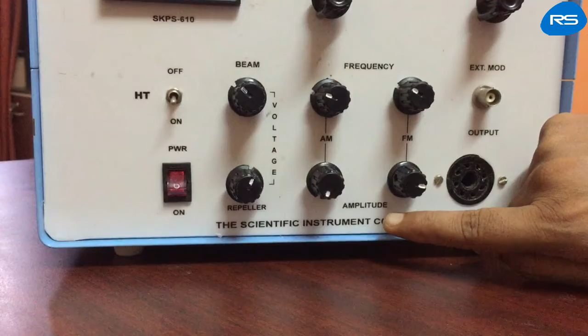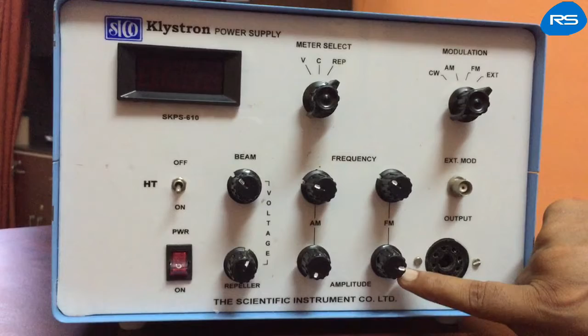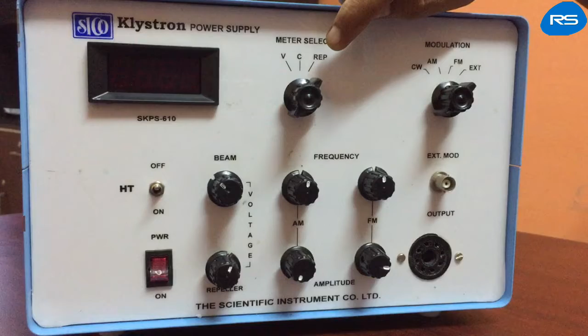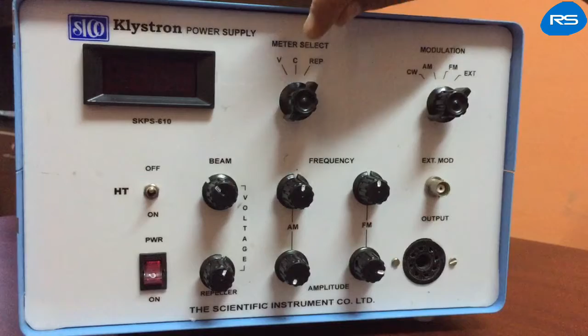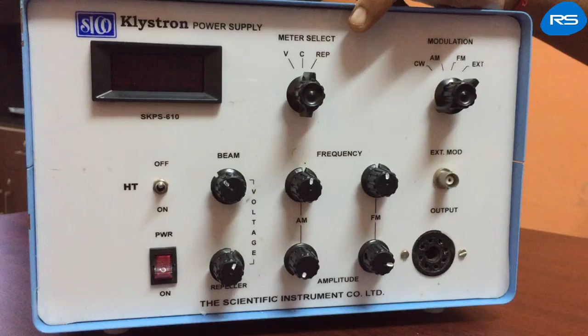Amplitude. AM adjusts the amplitude of the AM modulating signal. FM adjusts the amplitude of the FM modulating signal. Frequency. AM controls the frequency of the amplitude modulating signal from 500 Hz to 1500 Hz approximately. Meter selector. V position to measure the beam voltage of the supply in volts at DPM. C position to measure the beam current drawn by the Klystron in milliamperes at DPM. REP position, repeller position, to measure the repeller voltage applied to the Klystron tube at DPM.